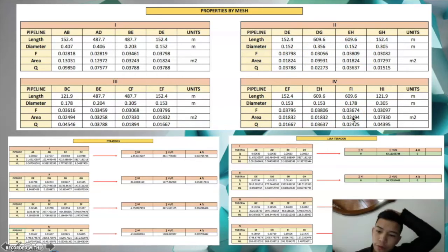Following Cross theory, a zero flow delta must be completed as the main principle, so four iterations are performed, and the following iterations are carried out in order to comply with the theory. Rigorous iterations are performed to conclude a single zero in the flow delta.